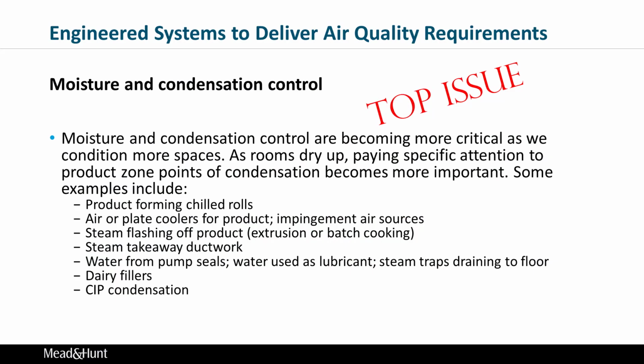These air handlers are critical in doing that. So once you get into designing these systems, it's important for the HVAC engineer to talk to the client and get an understanding, either see a similar space to the one that's going to be designed or built, or if it's an existing facility that needs to be fixed in some way, get out there, look at it, have a conversation with the building owner, the plant manager, and all the people on staff that know how the building operates and the process operates, and go through where all these sources are.